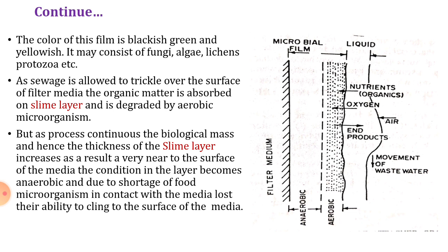In the anaerobic zone, microorganisms do not get sufficient oxygen and nutrients, so they die because of the shortage of food, and due to which the biofilm loses its ability to attach to the filter media and it starts sloughing or breaking up.